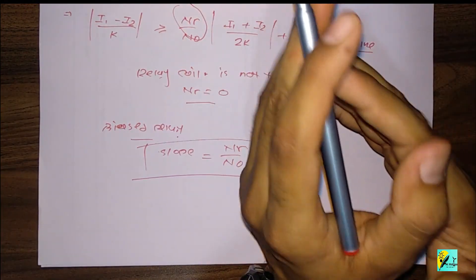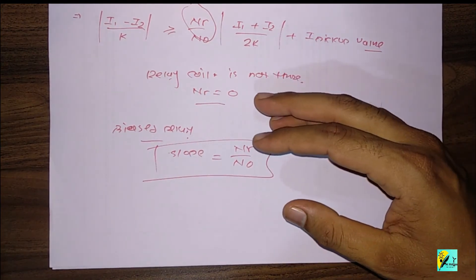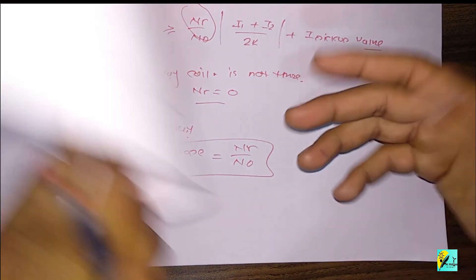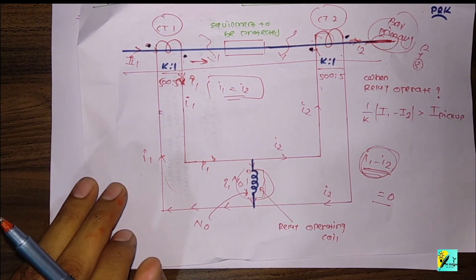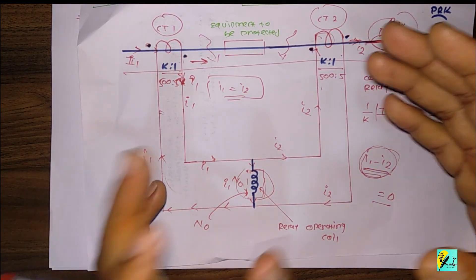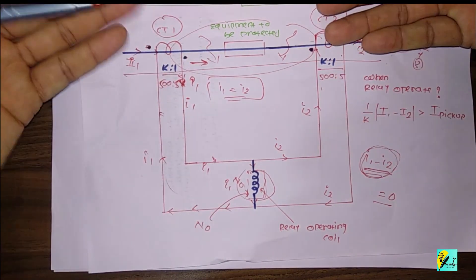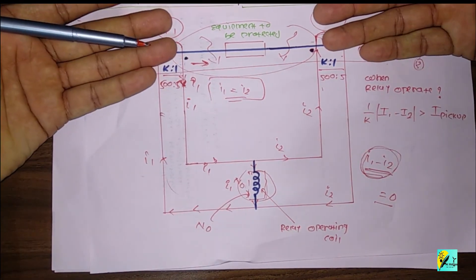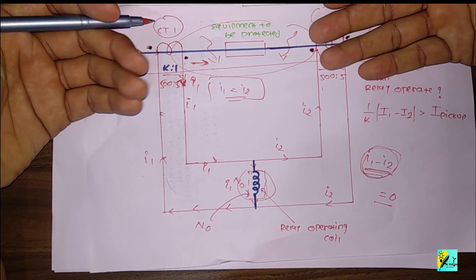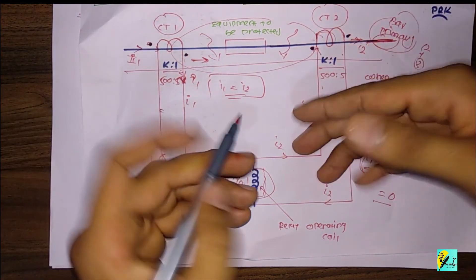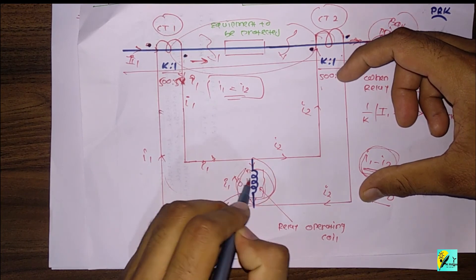This is called a biased relay, or you can say percentage type or slope type relay. The slope is Nr/N0. So if we use simple differential protection, it can mal-operate when there is no fault, or when CTs saturate or are not identical in nature.